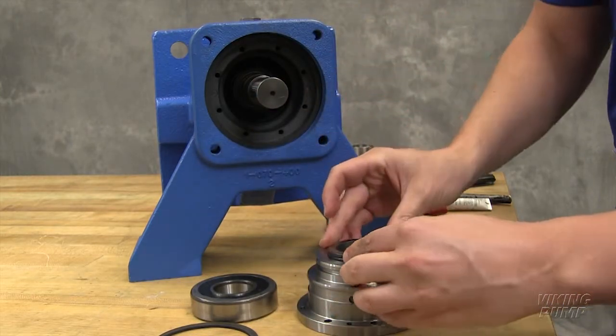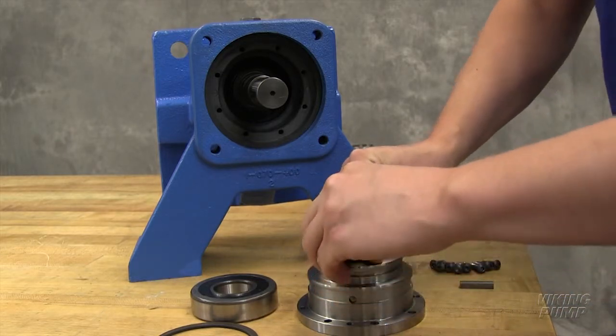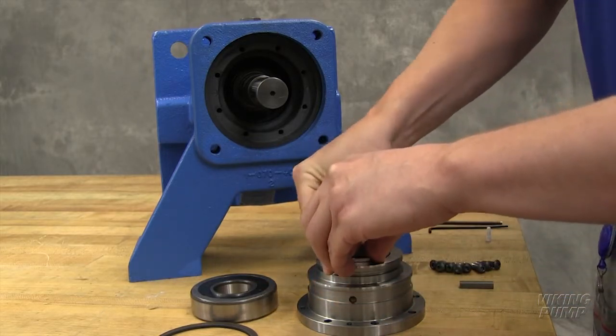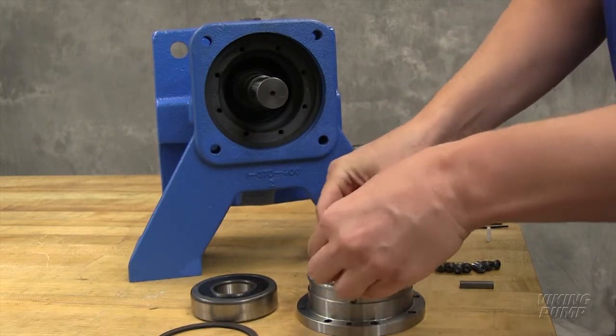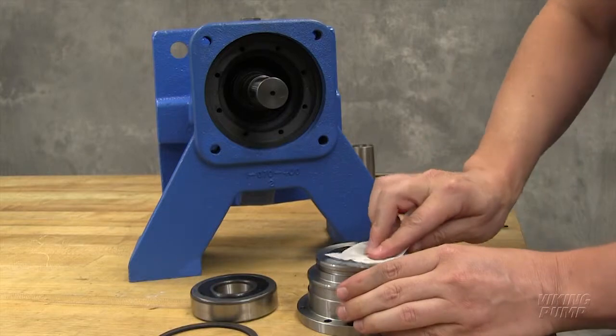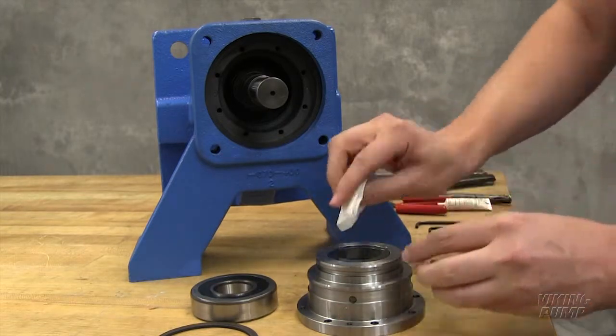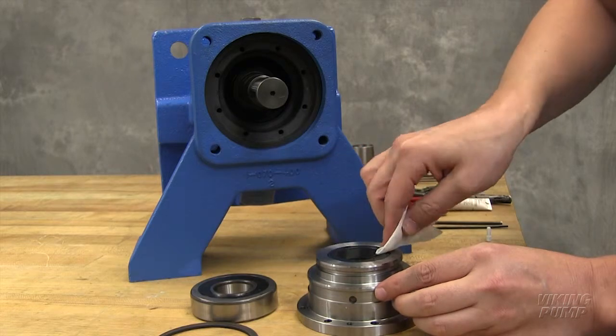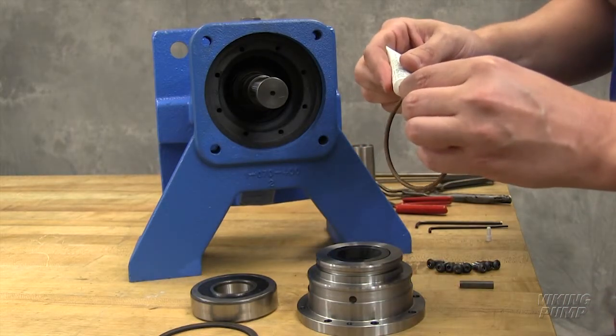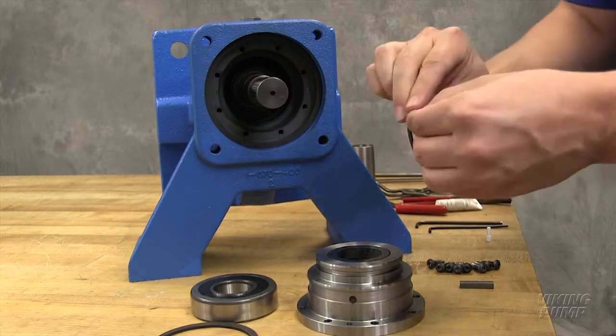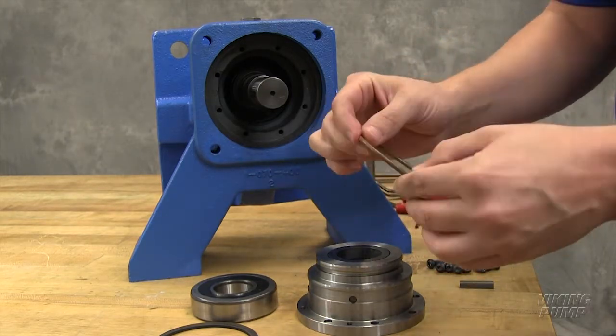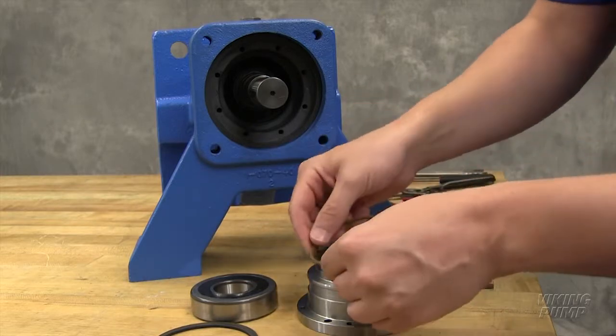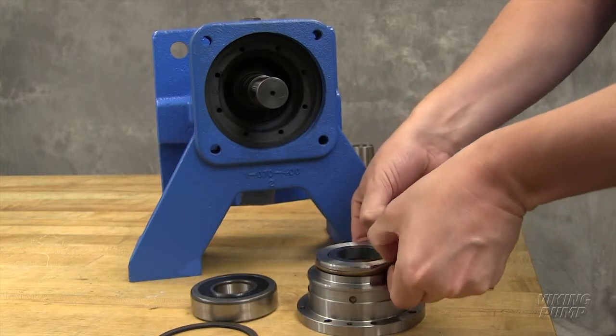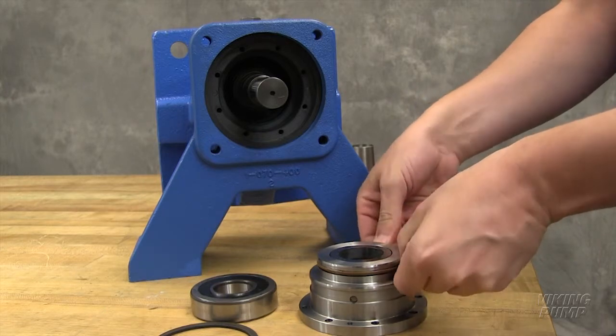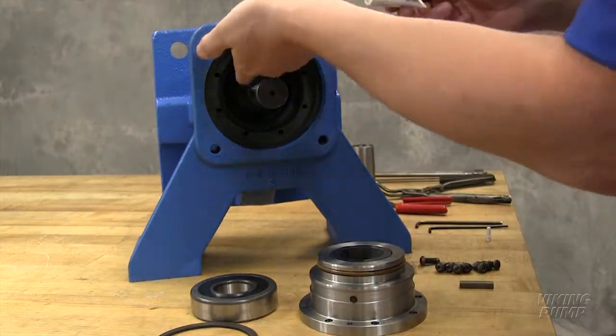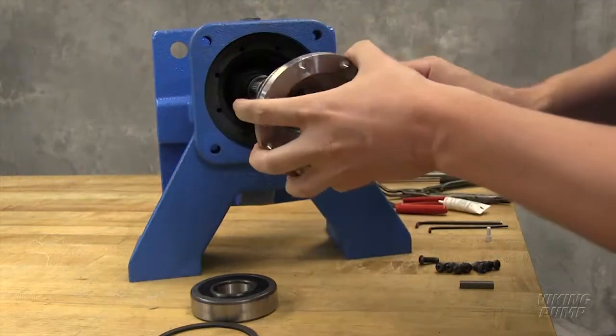Remember, the face of the stationary seat has been lapped to a mirror finish. Any damage done to this face during installation will affect the ability of the mechanical seal to seal. Wipe the seal face clean with a lint-free towel. Lubricate the O-ring with a light oil and place it into the seal holder groove. Lubricate the pump bracket bores with a light oil and install the seal holder.